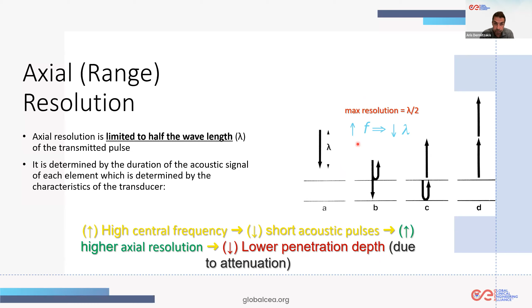What I can do, as we said before, we can use higher frequency, because higher frequency means lower wavelength. So higher frequency, lower wavelength, so it means short acoustic pulses, higher axial resolution, but higher frequency has also the toll of lower penetration depth, because we increase attenuation, as we said. So we have shorter waves, we have better axial resolution, but we cannot see very deep. Then let's go to the lateral.